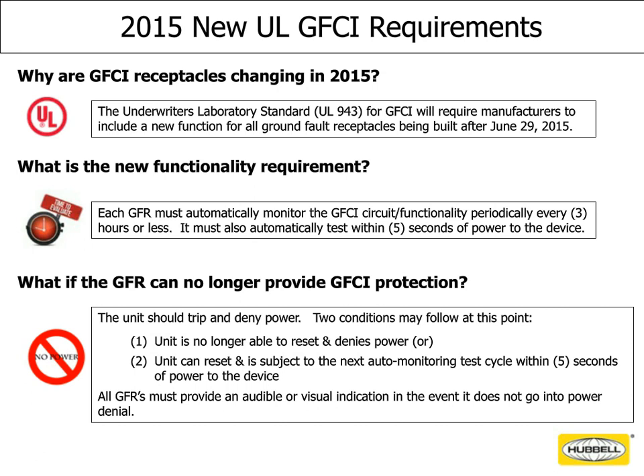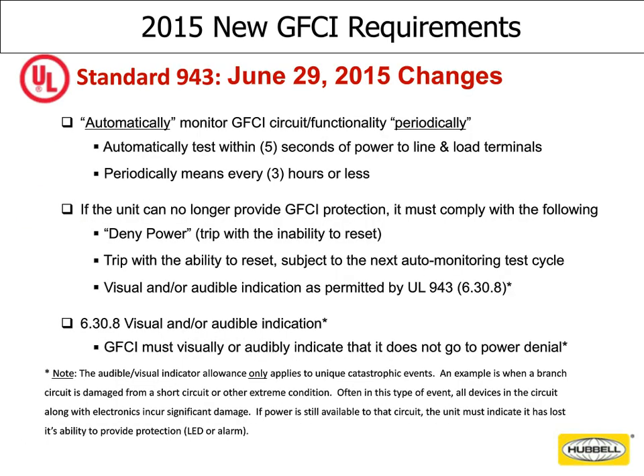The new UL standard impacts every single manufacturer of ground fault receptacles, and it's going to virtually change every receptacle on the market today. So as of the 29th, Hubbell will no longer be allowed to manufacture any of the ground fault receptacles we make today, and that goes for all of our competitors as well. So every single ground fault will change. The new product must have what we call a self-testing feature to it.